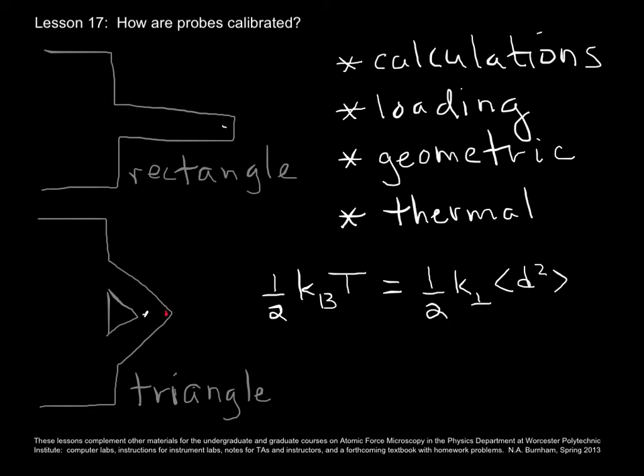This approach is becoming more and more common because it's pretty easy to do, and more AFM manufacturers are including the software routine in their instruments. You do have to assume that your cantilever is driven only by thermal energy. That is, there is no vibration coming through to it, it's acoustically isolated, the laser that you're using to illuminate it and detect its position is not heating it up, etc. I'll also note that there are a couple of dozen, perhaps, methods of calibrating the torsional spring constant, but I think we'll save those for an advanced lesson someday.